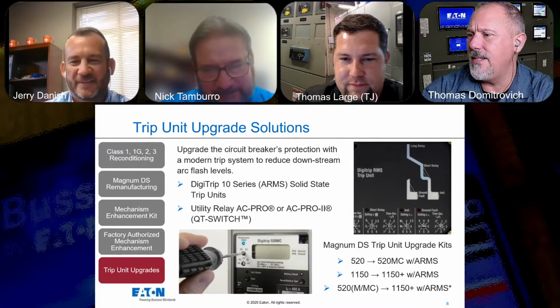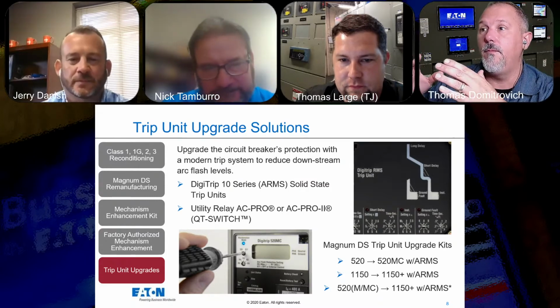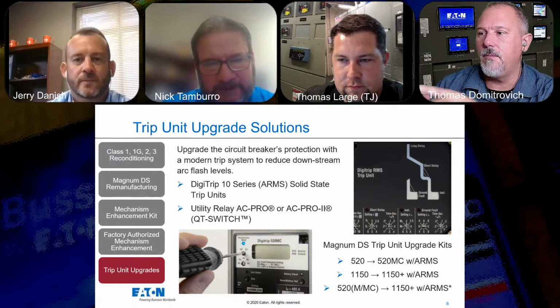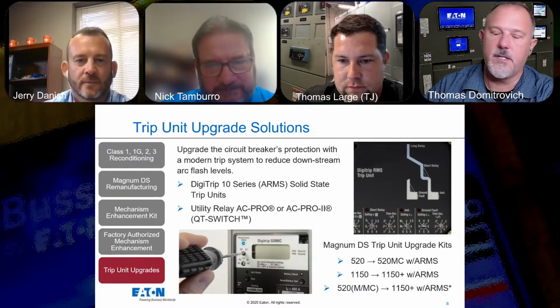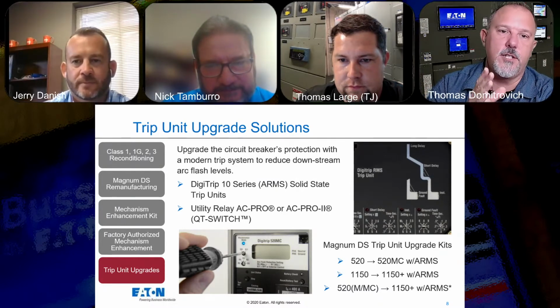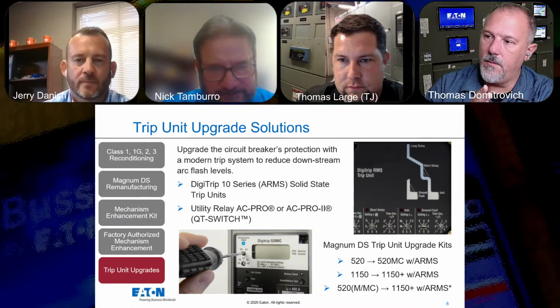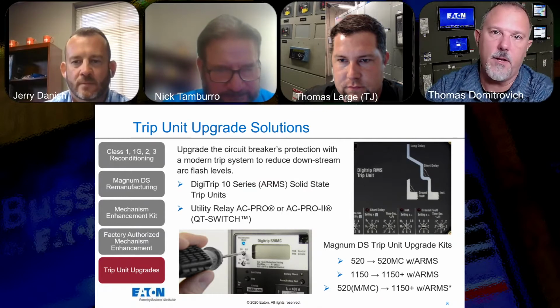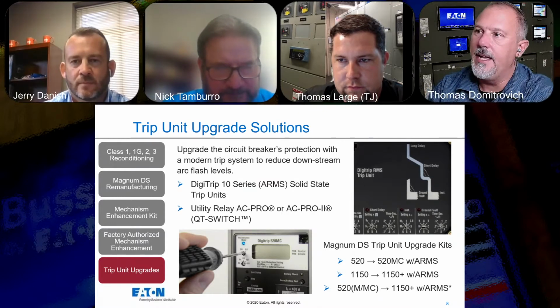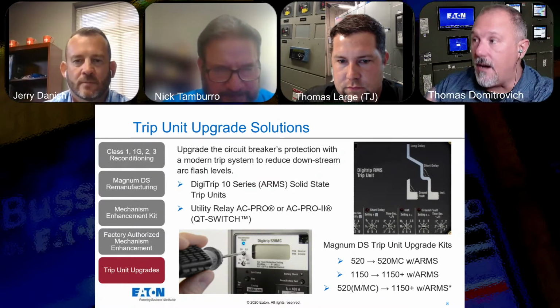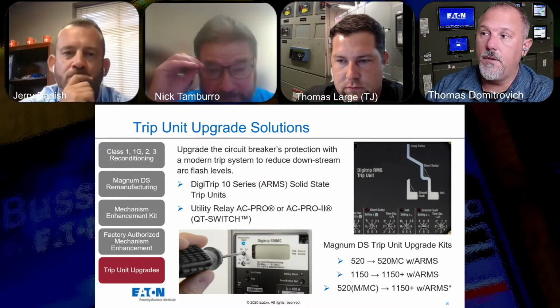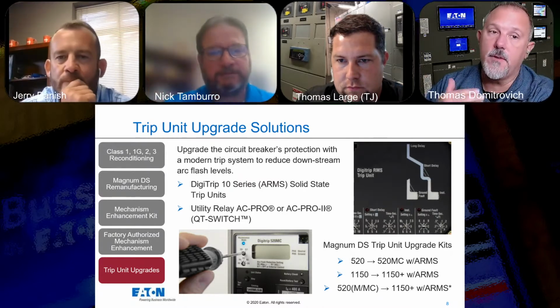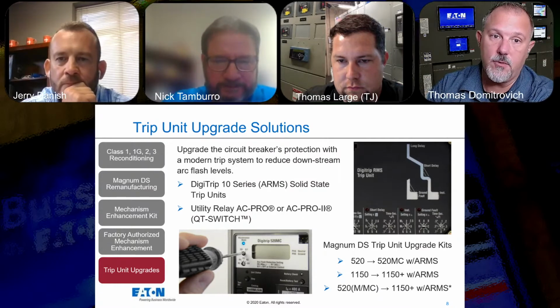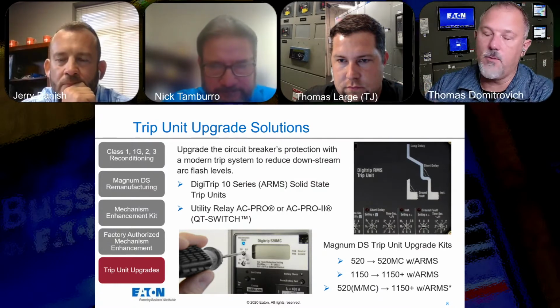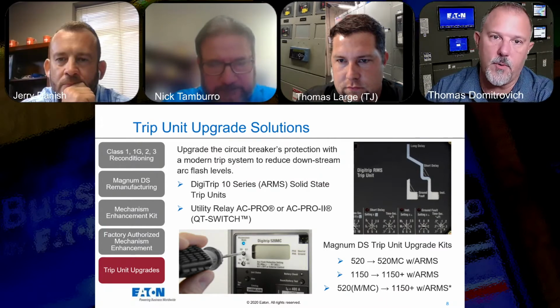All right. So this is the trip unit. I'm a big proponent of this because of the arc reduction maintenance switch technologies. I think for the electrical worker, that's the cat's meow. I mean, it reduces incident energy considerably. And I get this question a lot when I talk about the value of reducing the clearing time of an arcing current and the amount of energy you're reducing. I get the question of, can I put this on my older breakers?